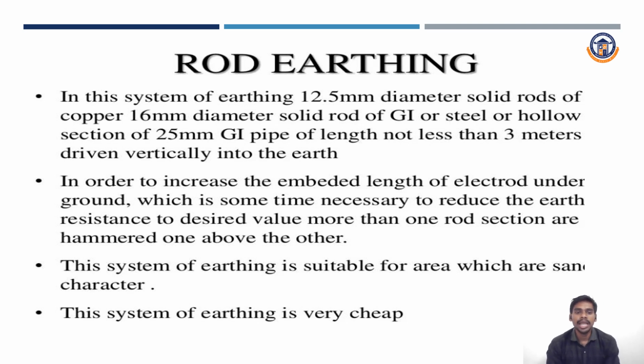Next one is rod earthing. In this system of earthing, 12.5 millimeter diameter solid rods of copper, 16 millimeter diameter solid rods of galvanized iron or steel, or hollow sections of 25 millimeter galvanized iron pipe of length not less than 3 meters are driven vertically into the earth. In order to increase the embedded length of the electrode underground, which is sometimes necessary to reduce the earth resistance to the desired value, more than one rod section is hammered one above the other. This system of earthing is suitable for areas which are sandy. This system of earthing is very cheap.